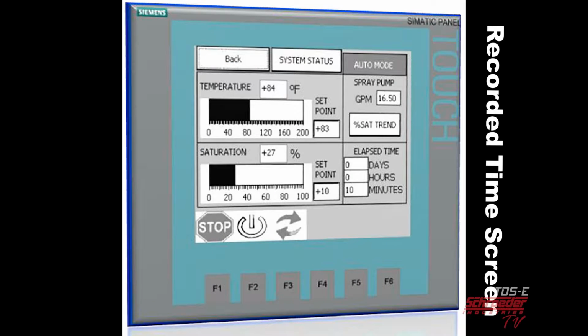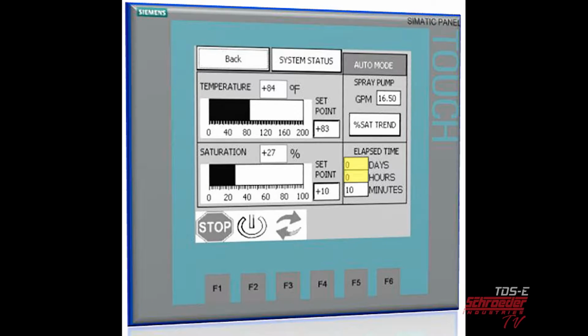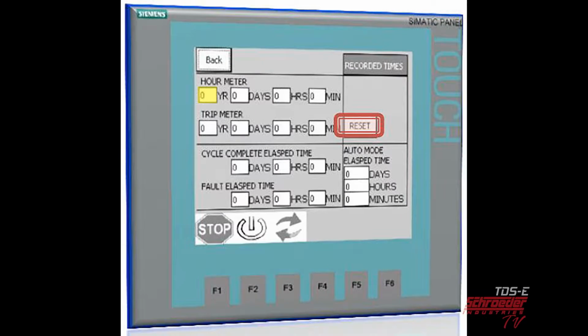The recorded time screen can be accessed by clicking below elapsed time on the auto mode screen. Hour meter records the total operation time of the Triton. Trip meter enables a reset operation timer, which is useful for preventative maintenance schedules. Cycle complete records the time the Triton has remained inoperative due to the fluid's saturation point being below the user's set point. Fault elapsed time records the time the Triton has remained inoperative due to a system fault. Auto mode elapsed time records the time the Triton has operated continuously in auto mode. The timer automatically resets each time a new cycle is started.